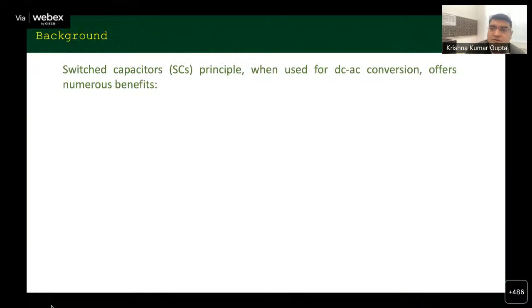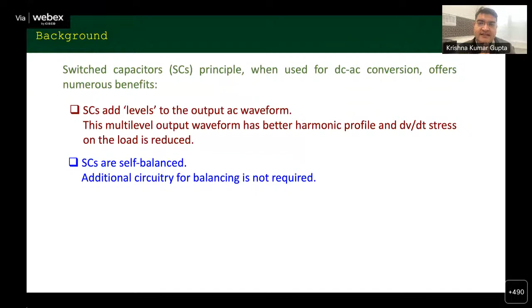Since only one capacitor is required, the overall count is less. What happens here is we use a switched capacitor principle, meaning a capacitor in the converter comes in parallel with the DC source to get charged, and then is connected in series for discharge. Because of this, levels are added to the output AC waveform, so it becomes a multi-level inverter, which adds to the life of the motor because the dV by dt stress on the load is reduced. An important advantage is these switched capacitors are self-balanced because you bring them in parallel with the battery - you don't have to add additional circuitry for balancing.